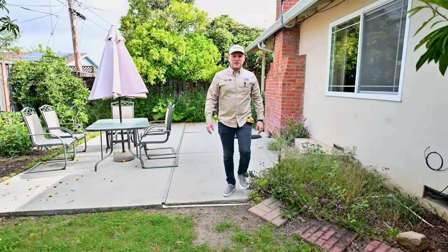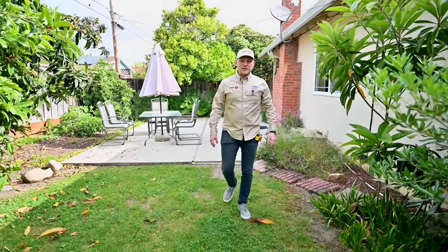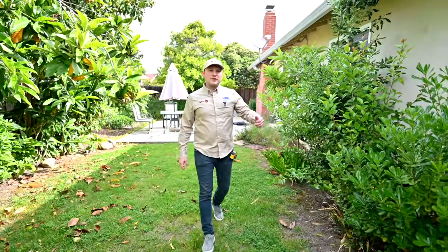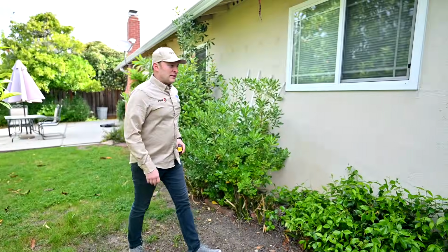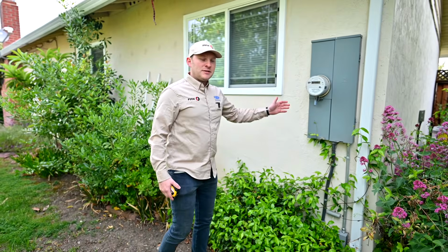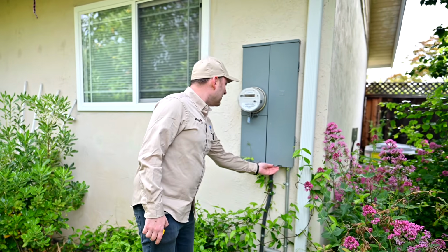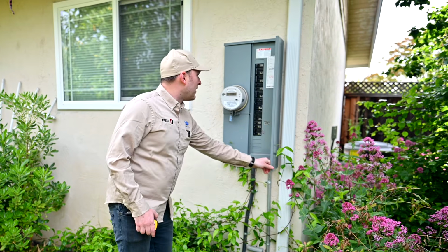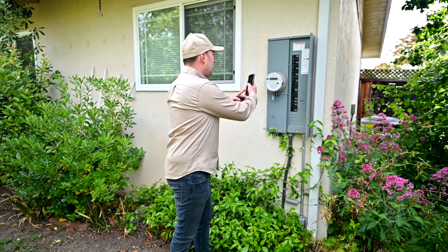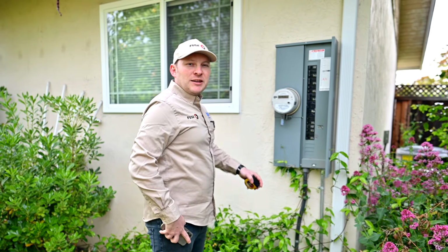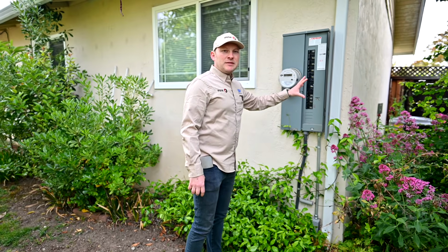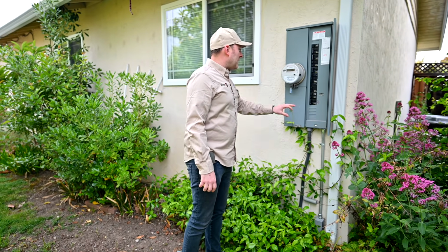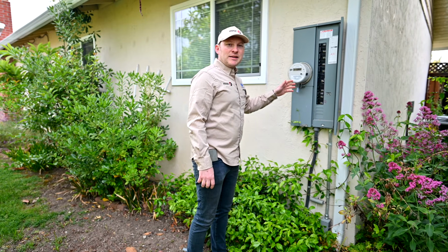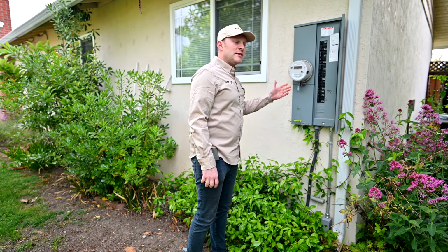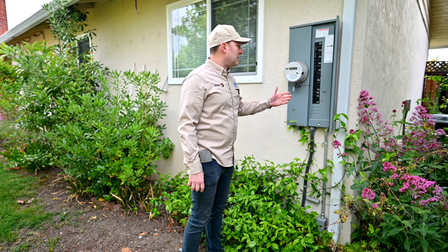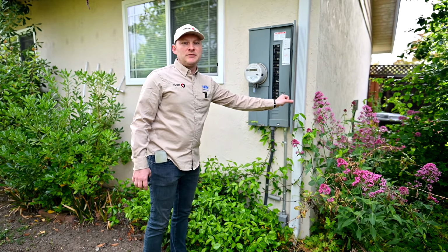Next up, we need to check your electric panel to make sure the new equipment we install will comply with all requirements, that your panel is not overloaded and doesn't have any safety hazard issues. We'll take a look at the panel and take some photos, as we need to do the load calculation. Sometimes the panel is overloaded or extremely old and poses a safety hazard for the new installation. In that case, we would offer you a replacement option to install a new panel.